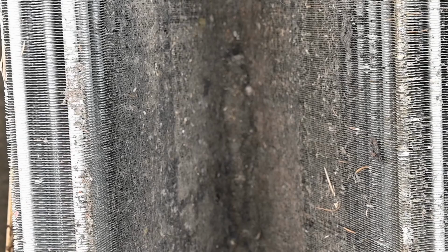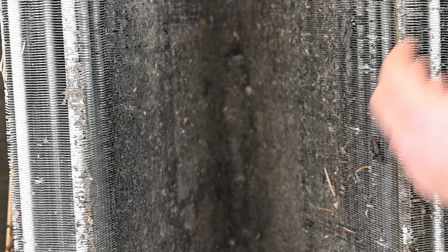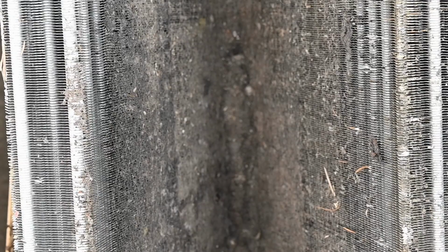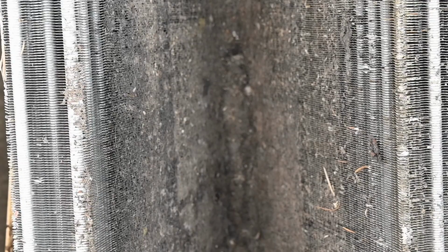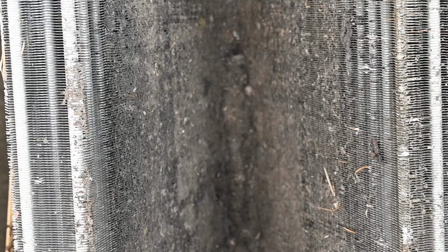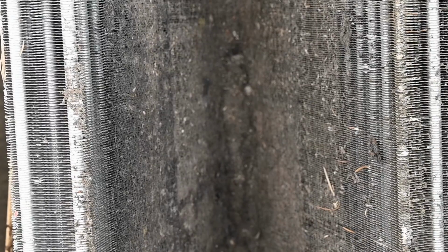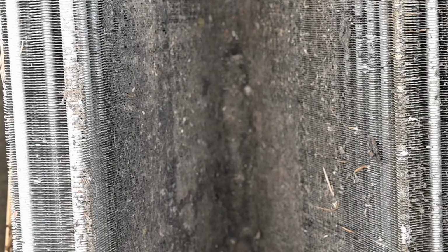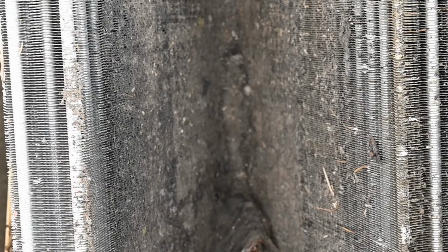Instead of dripping into the drain pan, it's dripping past into the blower, or if it's a negative return, it's dripping down onto the filter. So a lot of times you have a dirty filter, and well, it started doing this after the guy cleaned the coil. If you try to clean them in place, that is one of the issues that we really worry about. And I don't think the camera is doing this justice. I mean, this is absolutely horrible. Look at this.